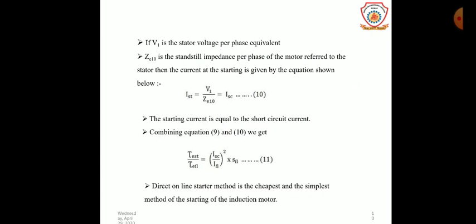Now, if V₁ is the stator voltage per phase and Z_E10 is the standstill impedance per phase of the motor referred to the stator, then the starting current is given by I_starting = V₁ / Z_E10 = I_SC — the starting current equals the short circuit current (Equation 10). Combining Equations 9 and 10 gives Equation 11. Thus, the direct-on-line starter method is the cheapest and simplest method of starting an induction motor.